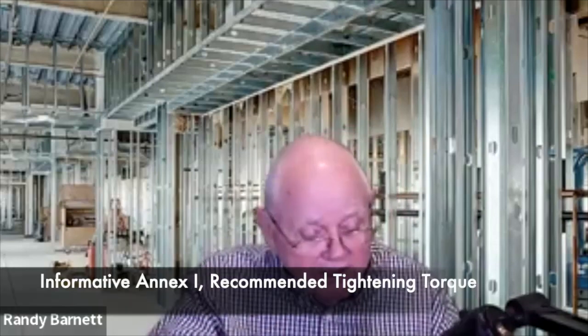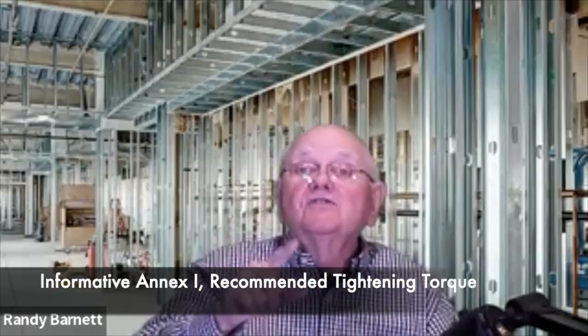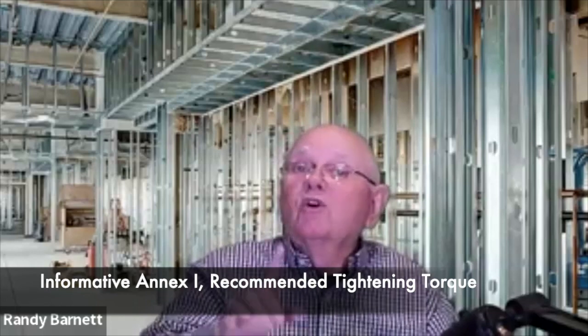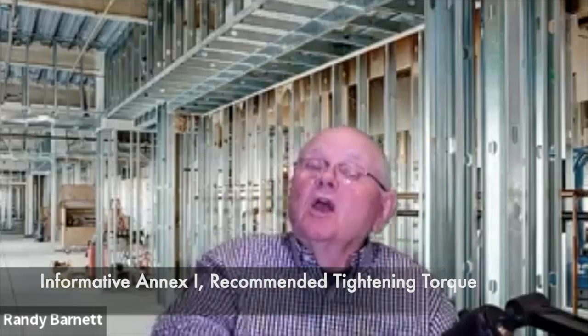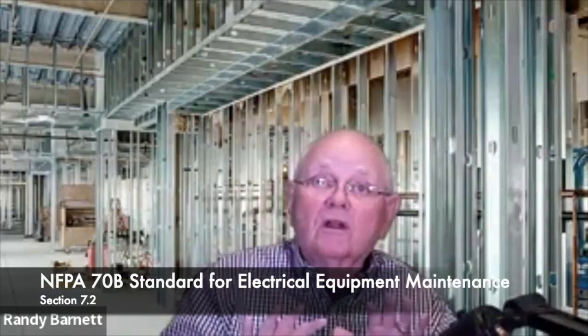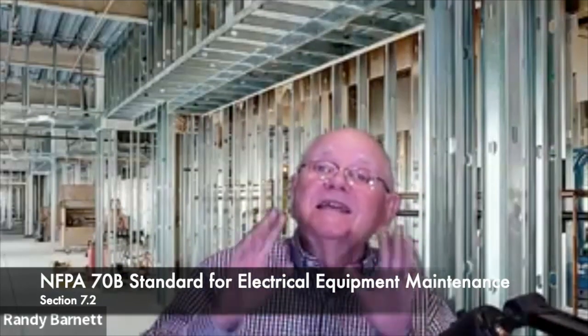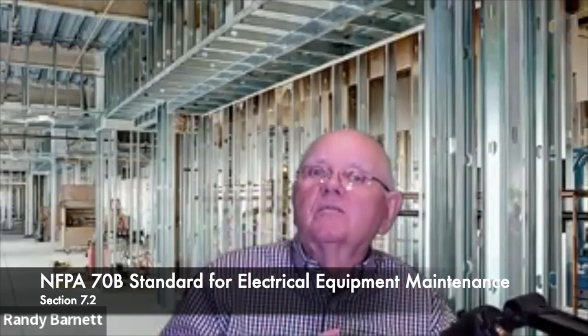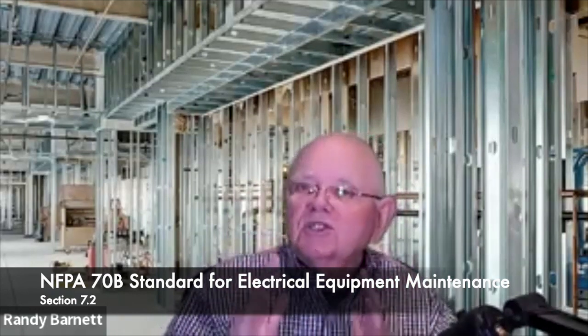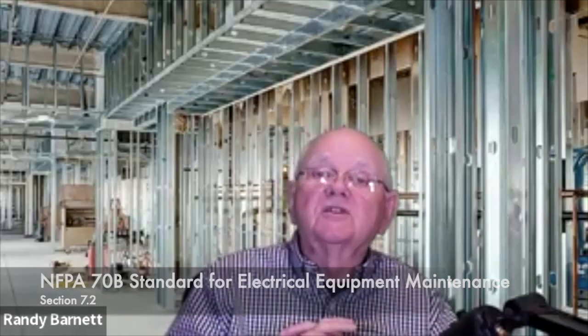Oh, by the way, informative Annex I in the back gives you torque values as well. Also, the NFPA 70B, which the code book references as a recommended practice, that's not true anymore. The NFPA 70B is now the standard for electrical equipment maintenance. And in section 7.2 of 70B, it has information on torquing and different ways that we can check torque requirements. All righty. So anyway, that's it for 110.14 electrical connections.